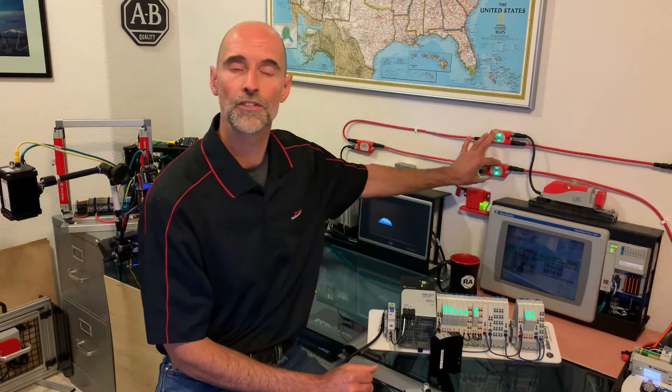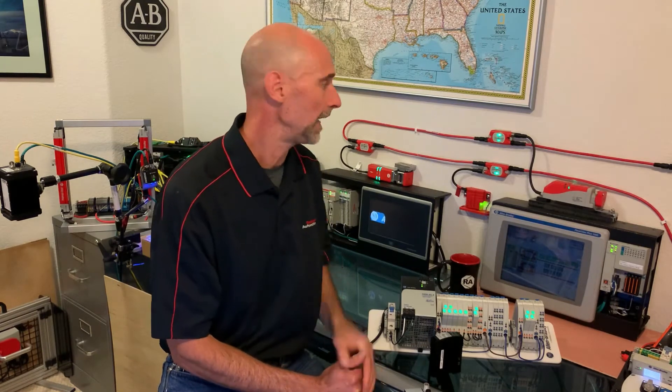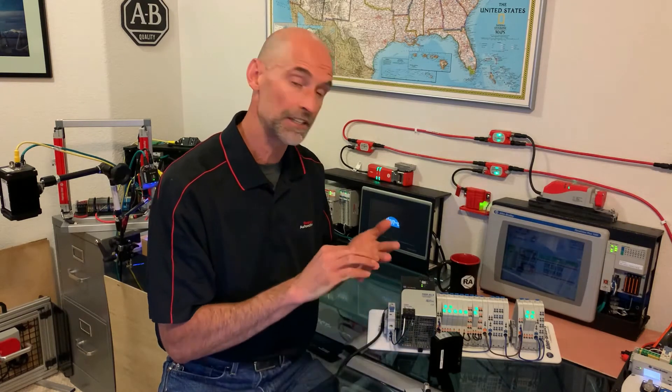So aside from pure compliance reasons, what are some benefits of complying with NEC Class 2? An end user or an OEM that specifies Class 2 devices experiences safer electronics and reduced PPE requirements. Device manufacturers such as ourselves can manufacture smaller and smaller devices while still achieving very high reliability ratings and the ability to achieve the highest safety performance levels. And since UL has a focus on those same two hazards that NEC Class 2 eliminates — specifically electrical shock hazard and fire hazard — a panel shop that supplies NEC Class 2 circuits for the termination of NEC Class 2 devices easily complies with that portion of their UL 508 code set.